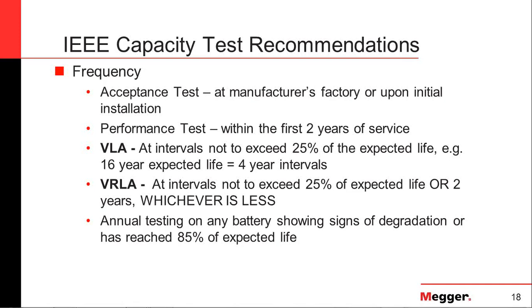Especially for us, our bite testers actually do that measurement for you, both the bite 3 and the bite 2. One with the CT clamp, one by going onto one of the straps and just measuring it. But generally speaking, what you need is an AC meter and some sort of clamp or some sort of way to get into the circuit or into the series path of the battery string.